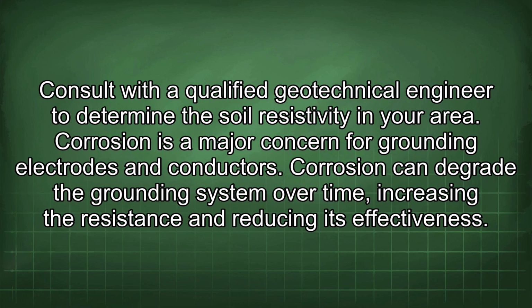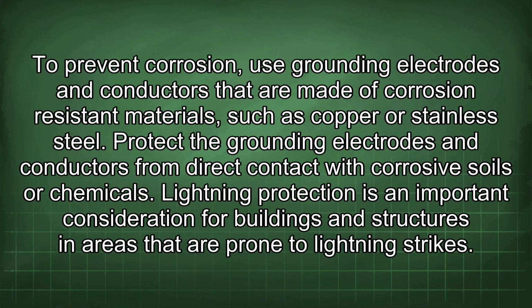Consult with a qualified geotechnical engineer to determine the soil resistivity in your area. Corrosion is a major concern for grounding electrodes and conductors. Corrosion can degrade the grounding system over time, increasing the resistance and reducing its effectiveness. To prevent corrosion, use grounding electrodes and conductors that are made of corrosion-resistant materials such as copper or stainless steel. Protect the grounding electrodes and conductors from direct contact with corrosive soils or chemicals.